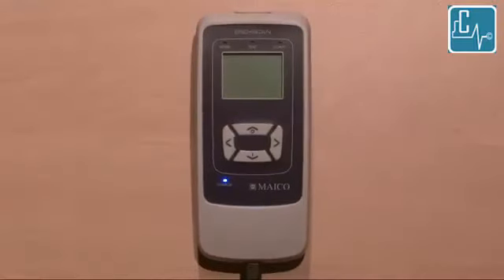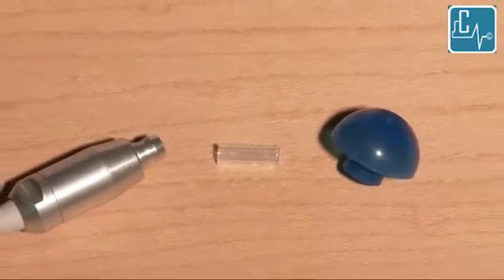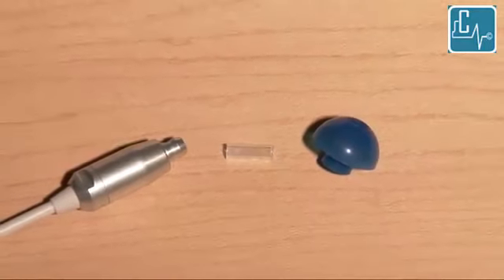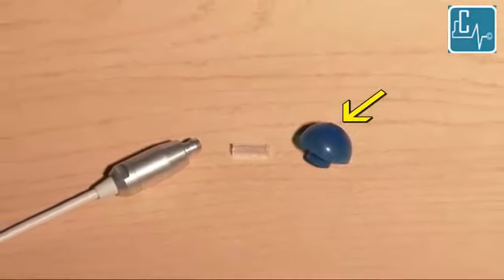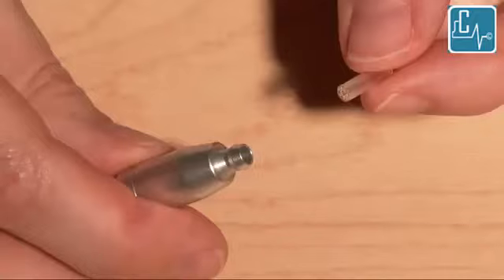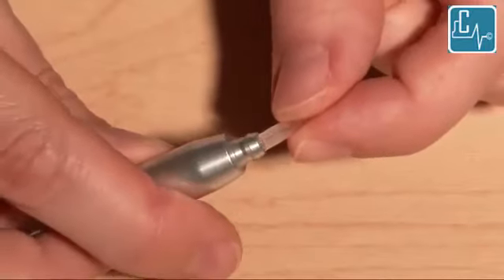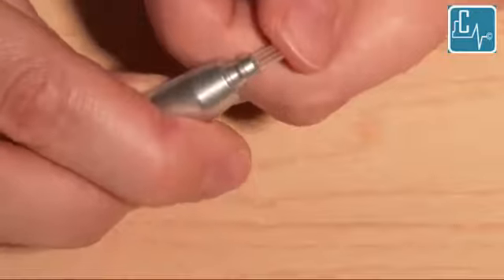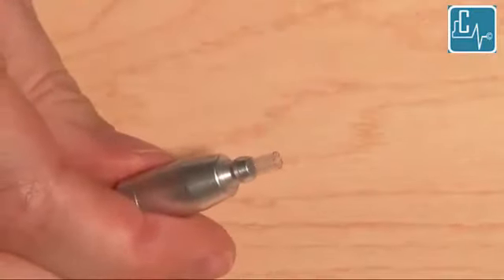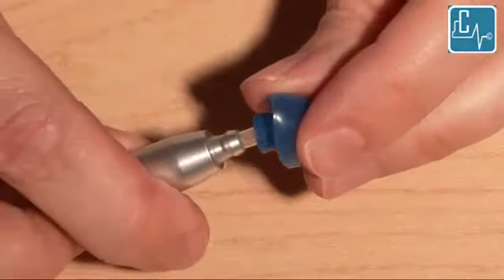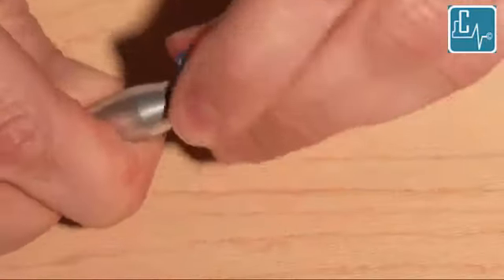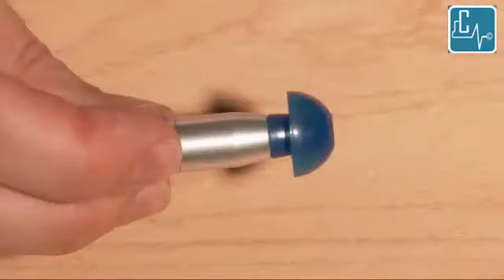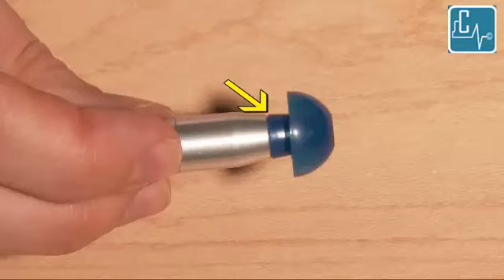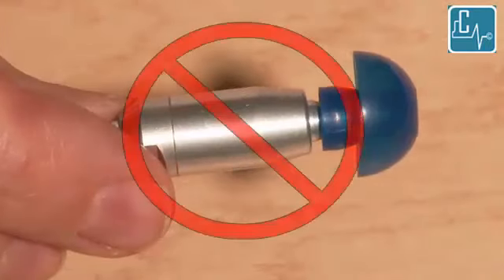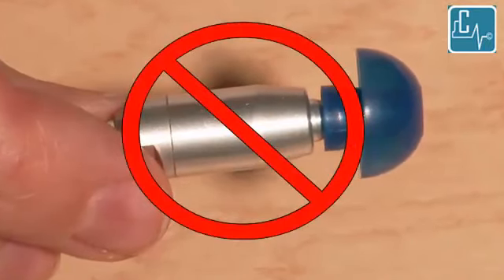Now let's review the parts of the probe itself. The probe consists of 3 main parts: the probe body, the probe tube, and the ear tip. A probe tube and ear tip must be used with the probe in order to conduct a test. Always make sure that a probe tube is in place before attaching an ear tip. Select an appropriately sized ear tip and insert the ear tip onto the end of the probe. Make sure the ear tip is fully seated onto the probe. There should be no gap between the base of the ear tip and the body of the probe. If the ear tip is not fully seated, this may affect results of the test.